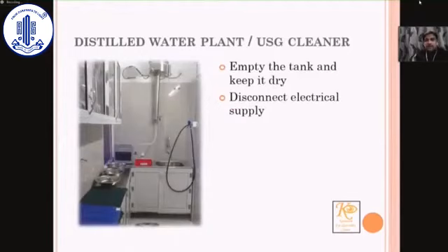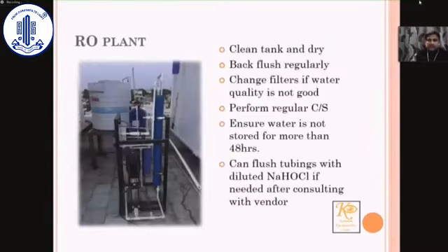If you have an in-house distilled water plant, make sure during decommissioning you cut off the water supply and also dry the water still if you're not planning to use it for more than 4 days. Do not store any water in the operation theater for more than 4 days continuously. Try to use it for cleaning purposes or any other activity at the earliest. The RO plant, if you have one in your hospital, however small or large it may be, has to be cleaned as per the protocol.